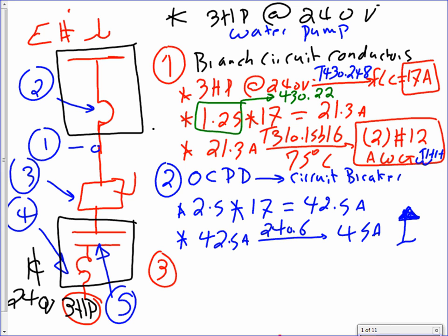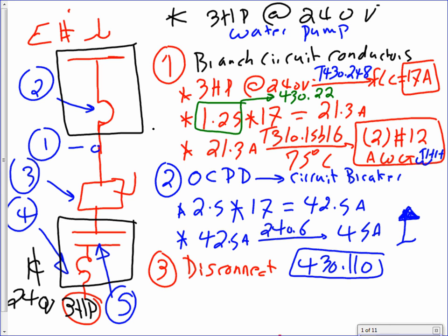Number three is the disconnect. Why do we need the disconnect? To safely isolate the system so we keep 10 fingers and 2 hands. Number one, and also don't get shocked. For the disconnect, guys, I'm not going to take you to the NEC code book. Here's 430.110. Your reference for the disconnect size is 430.110. If you go there, it tells you 1.15 times 17. This is 19.55 amps.